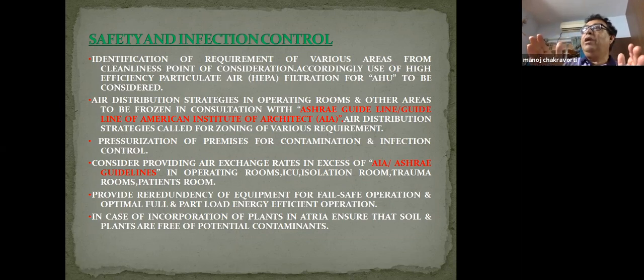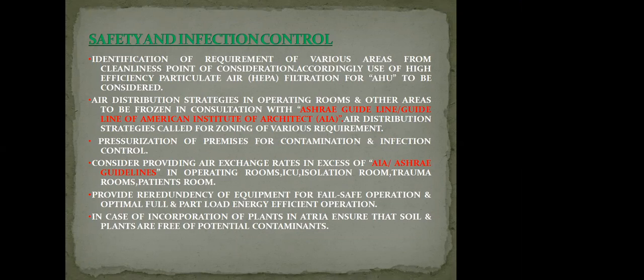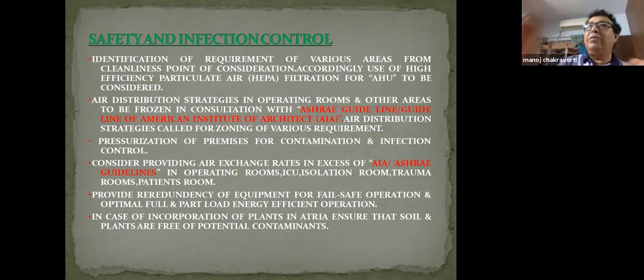In some areas we need a sterile zone, in some areas normal. Wherever we need a sterile zone, we need higher pressure, meaning air from outside that zone should not come inside — air can only go outside from that zone. Why? Because these are critical areas. Outside may have two-stage filtration, while here there may be three-stage filtration, so why contaminate that area with outside air?